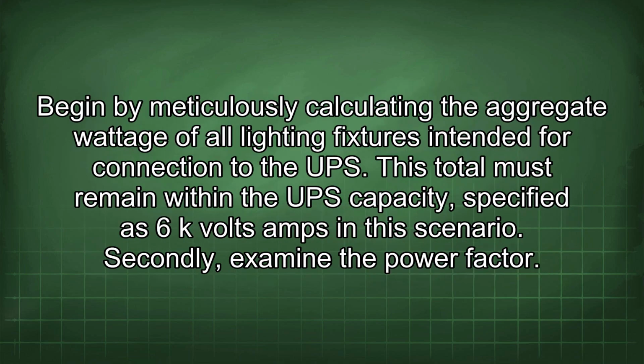Begin by meticulously calculating the aggregate wattage of all lighting fixtures intended for connection to the UPS. This total must remain within the UPS capacity, specified as 6 kVA in this scenario.